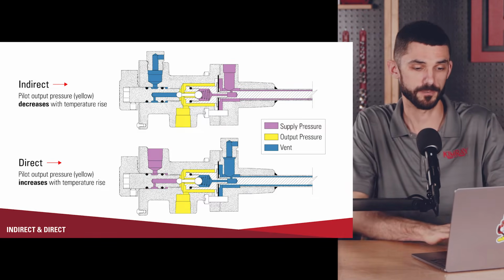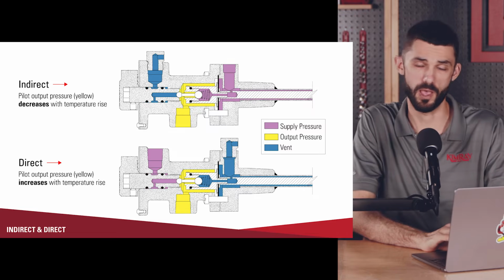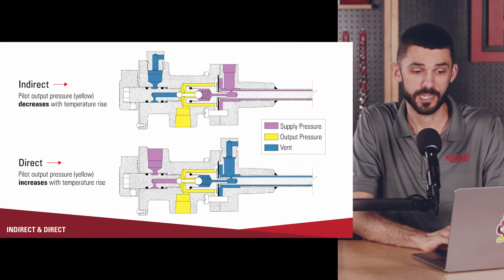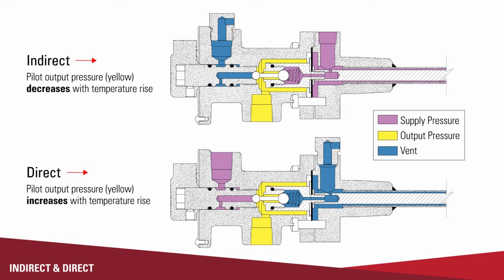So if we look at this example right here, the purple is the supply. So on indirect acting, the supply is coming into the connection closest to the vessel. The output remains the same whether you are in indirect acting or direct acting mode, but the vent on an indirect acting temperature controller will be the connection furthest away from the vessel. Now, if you look down below, we've got a direct acting temperature controller, and all that has happened is the supply and vent have changed places. So now the connection closest to the vessel is the vent, and the connection furthest away from the vessel is where you bring your supply into.